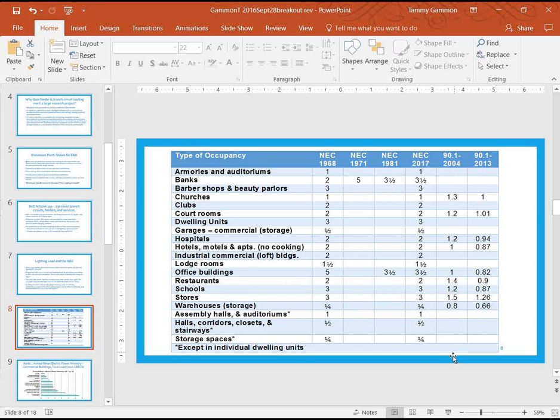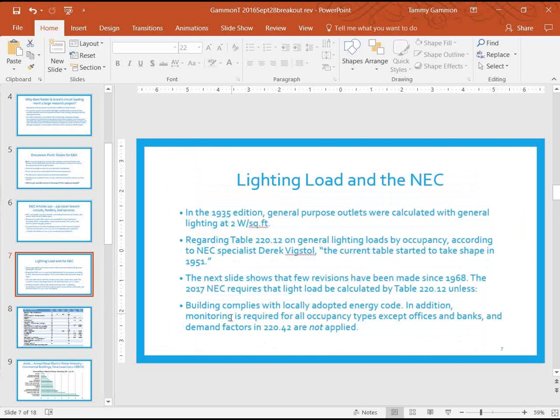Also in NEC 2017, if we go back to the last slide, there's finally an exception stating that if the building complies with a locally adopted energy code - I believe for offices and banks, I'd need to double check - then they can use the requirements in the energy code. But if it's not an office or bank, you have to have monitoring on your lighting systems, and in addition, the demand factors in 220.42 cannot be applied. Tam can enlighten us further when we get to this part, we can write it up with more specifics.